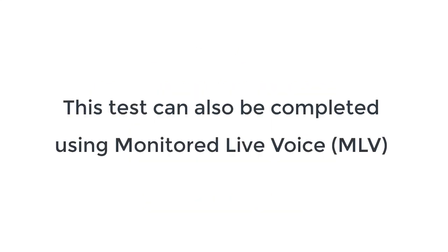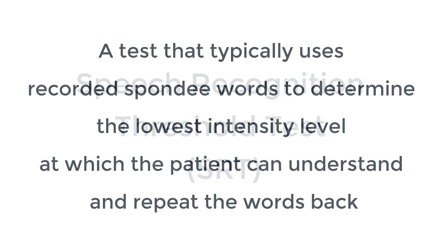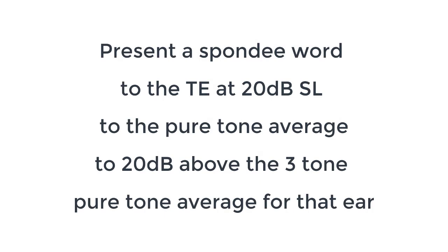The next type of speech testing is called the Speech Recognition Threshold test, or the SRT. This is also a test that typically uses recorded spondee words to determine the lowest intensity level at which the patient can understand and repeat the words back. You want to present a spondee word to the test ear at 20 dB SL to the pure tone average — 20 decibels above the three-tone pure tone average for that ear.